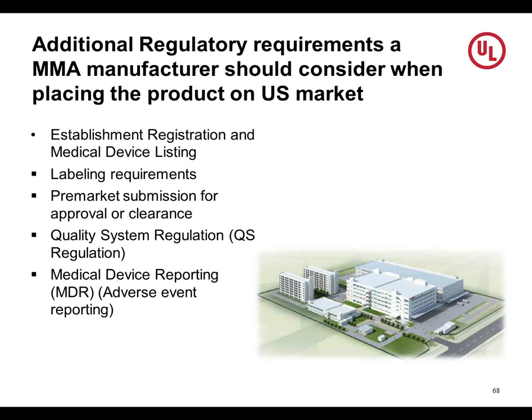But if they do, depending upon the risk profile, which would then help define whether the device is a Class 1 device, and we spoke to that in the context of a medical device data system, or possibly a Class 2 or Class 3 medical device, there are in fact additional regulatory requirements that a mobile medical application manufacturer would need to consider.